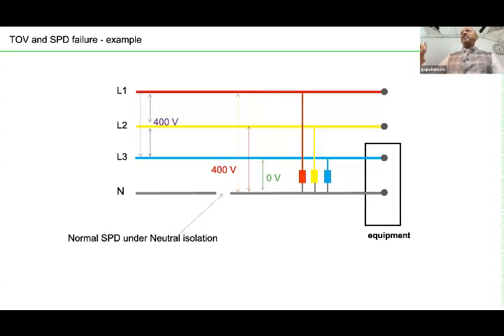Now what happens to the SPD in this condition is, two SPDs are stressed with 400 volt continuously for a longer time. As I said, SPD is a voltage operated device. There will be a leakage current, higher voltage, SPD rated for 230 volt, and the applied voltage is 400 volt. Higher current flows through this SPD, it heats up and it can catch fire. And a lot of fire accidents happen.